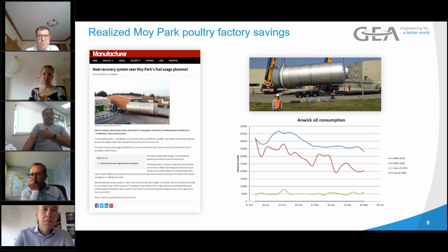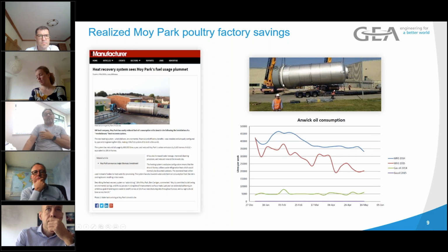If we just have a look at the client's own information, we shoved a great big buffer tank in, and actually that was reused from an old dairy. It's an old dairy tank of 350 cubic meters. The 4 boilers, 2 of them immediately switched off, and the other 2 reduced down to 50% loading. So we saved them 3/4 of their fuel consumption.